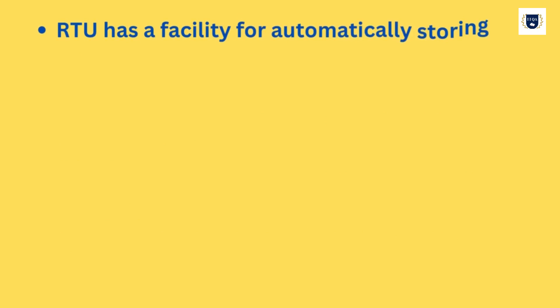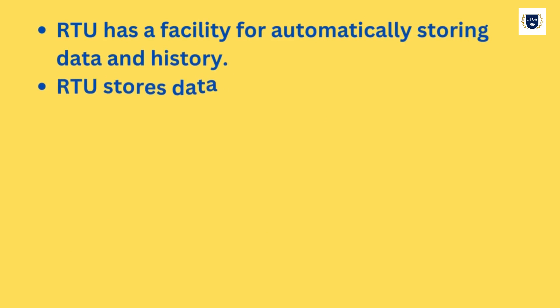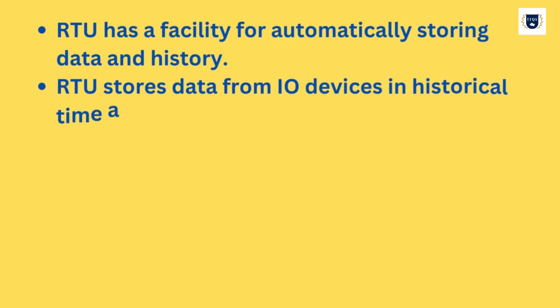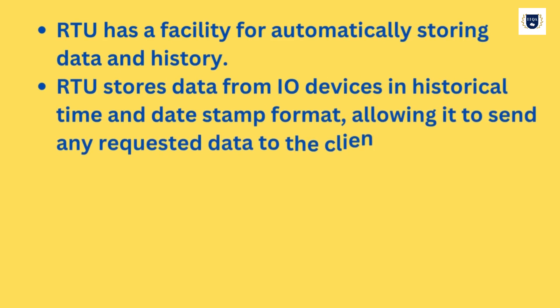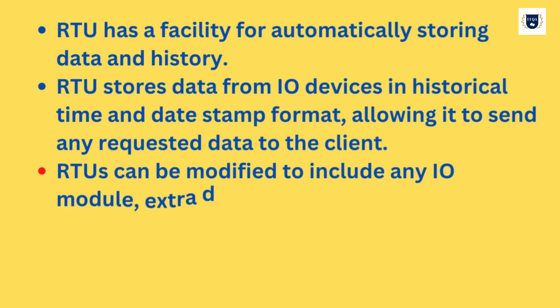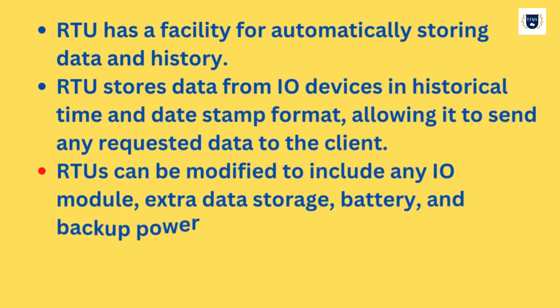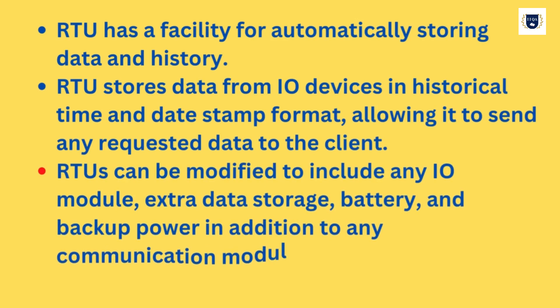RTU has a facility for automatically storing data and history. RTU stores data from I/O devices in historical time and date stamp format, allowing it to send any requested data to the client. RTUs can be modified to include any I/O module, extra data storage, battery and backup power, in addition to any communication module.